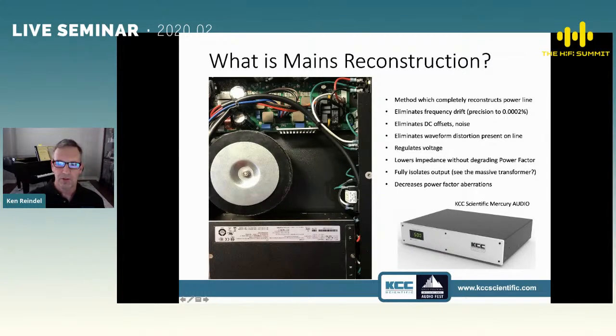We take the input line, turn it into DC, and then go back to AC again, completely reconstructing the power line. With that, we can get frequency drift that's very high precision, 0.0002%, a whole lot better than a percent. We clearly eliminate DC offsets and noise.